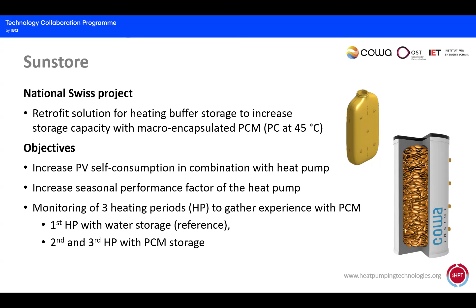And if you can limit it, for instance at 45 degrees, then the heat pump works at a better efficiency. Also, if you store more heat, you can shift the heat pump operation more to daytime, where you have a more favorable outdoor air temperature. In this case, it's an outdoor air heat pump which is installed. We have also installed this in a monitoring plant and measured three heating periods to gather experience with the behavior of the PCM. The first heating period served as the reference period, with a purely water storage for the heating buffer. In the second and third periods, the heat pump was equipped with different PCM elements, and we had some results on the operation of the PCM.